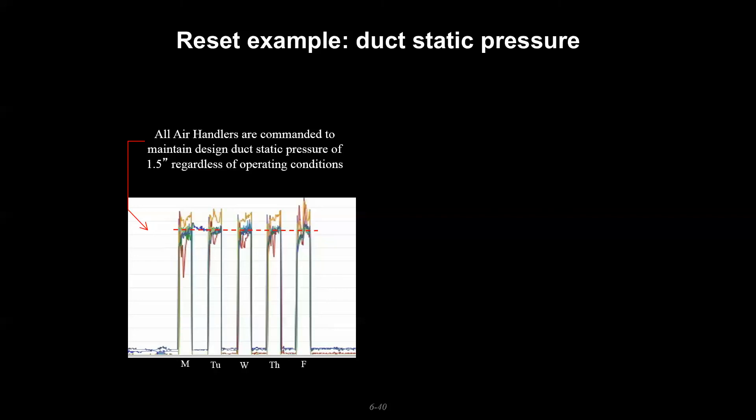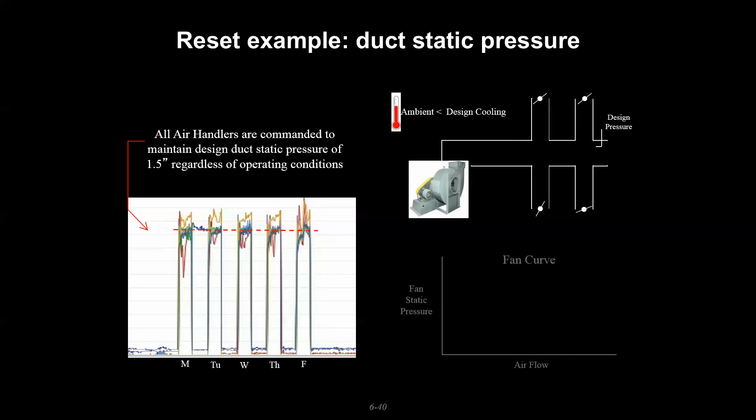By definition we're not going to see those design loads at all times, so what happens when we have a lot of boxes that have their damper closed? We have a system curve that's a little bit steeper and we're creating artificial pressure drop by having that duct static pressure setpoint so high. If we could reduce the duct static pressure setpoint or reset it down from one and a half inches to some smaller number, we'd be able to meet the CFM requirements at reduced pressure and have some fan savings.